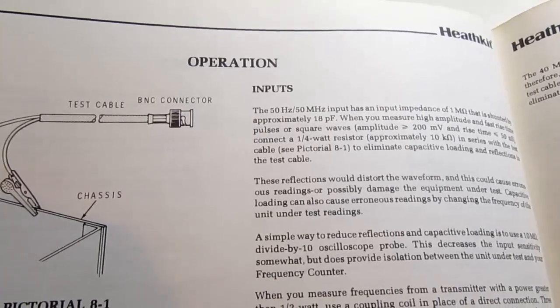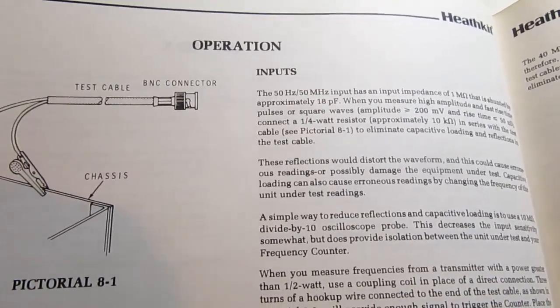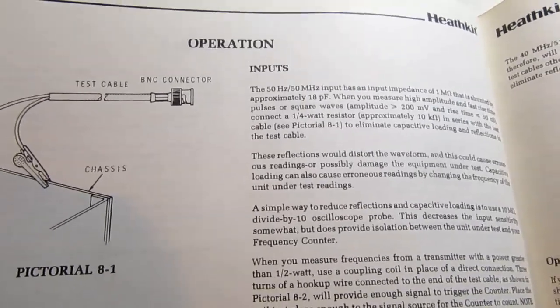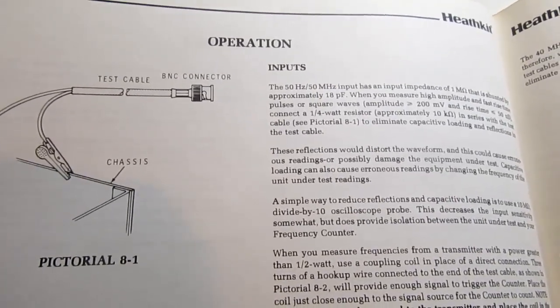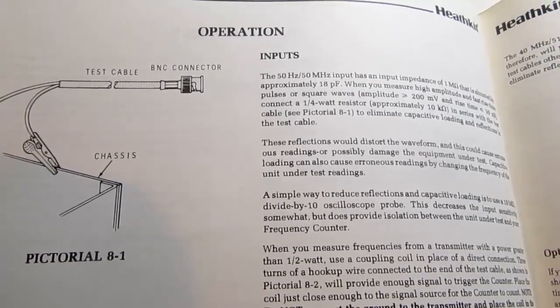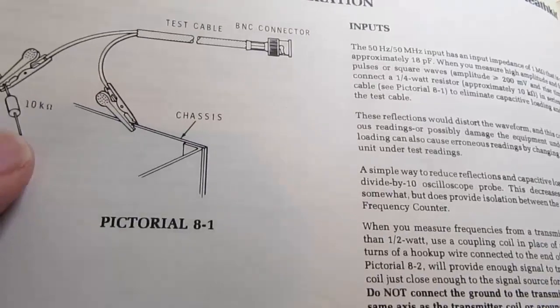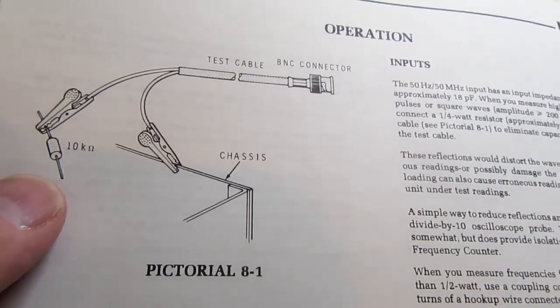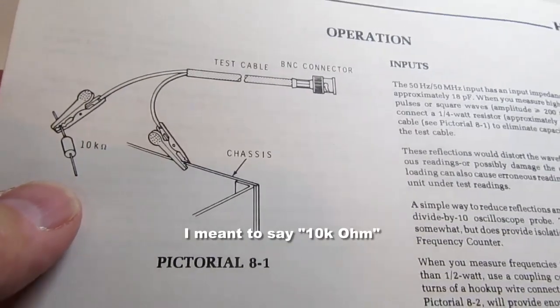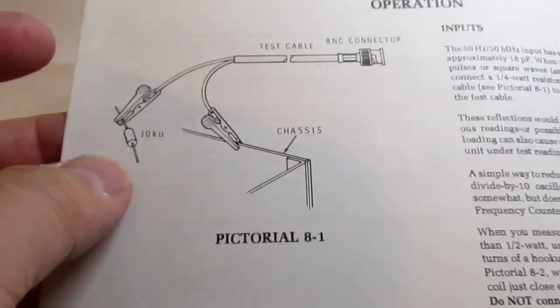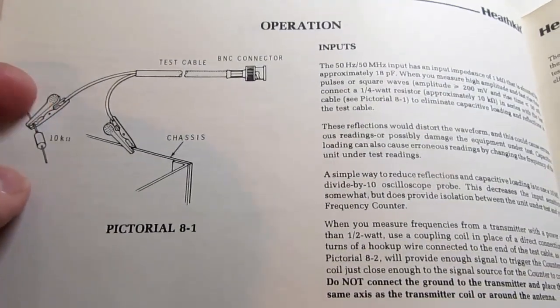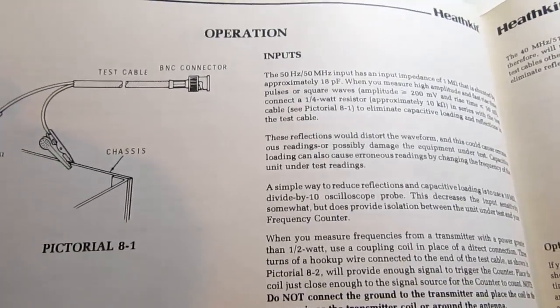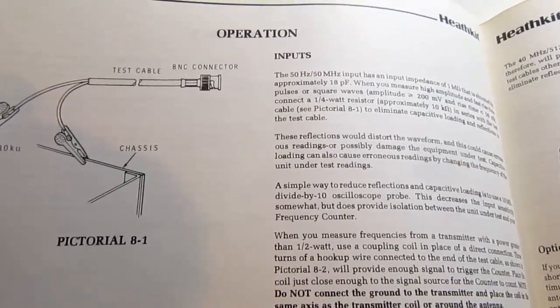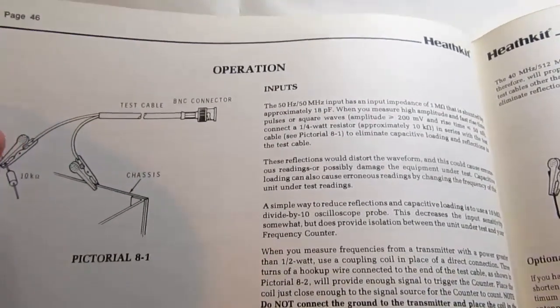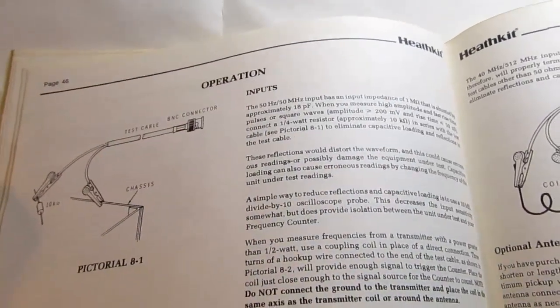If you're using the low frequency input with a 1 megohm impedance, when you measure high amplitude and fast rise time pulses or square waves with a high sharp rise time, then it's recommended you connect a small resistor, perhaps quarter watt, in the order of 10 kilohms, in series with a simple test cable, and use the other end of the resistor as the probe. That is due to reflections that you'd get with the fast rise times, which could cause erroneous readings or possibly even damage to the equipment under test, not necessarily the frequency counter.